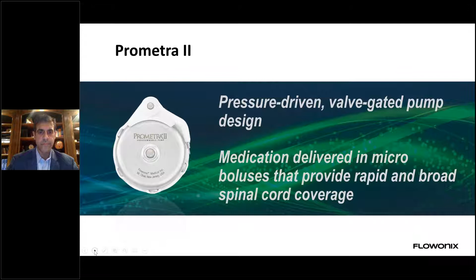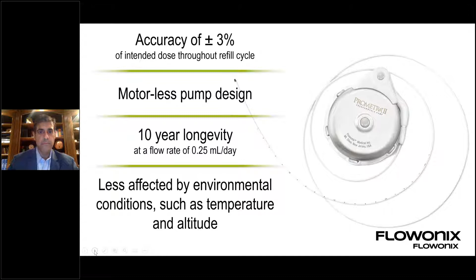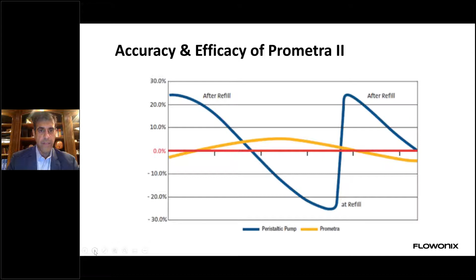The ProMetra 2 is 97% accurate throughout the refill cycle. There's no motor in this pump. It has a battery life of up to 10 years. And there's minimal effect on drug delivery by environmental factors such as temperature and altitude. Next slide. More specifically, looking at the accuracy of the ProMetra 2, there's really no variances throughout the refill cycle, as you can tell by the yellow line. Whereas with the peristaltic pump, there are some variances, up to 20% on output of drug, depending on reservoir volume, as you can tell by the blue line. Next slide.